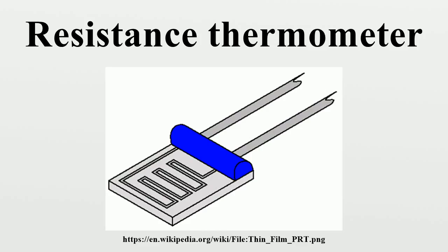Response time. If the process requires a very fast response to temperature changes, fractions of a second as opposed to seconds, then a thermocouple is the best choice. Time response is measured by immersing the sensor in water moving at 1 meter per second with a 63.2% step change. Size. A standard RTD sheath is 3.175 to 6.35 mm in diameter. Sheath diameters for thermocouples can be less than 1.6 mm.